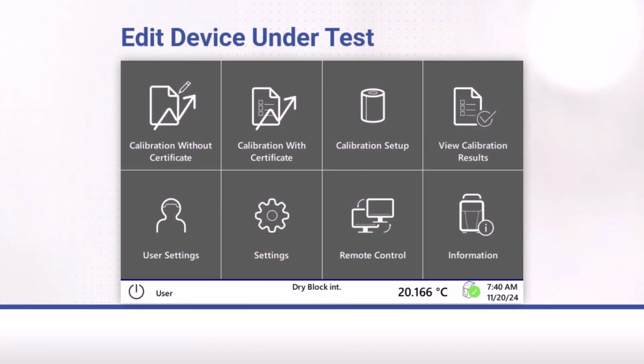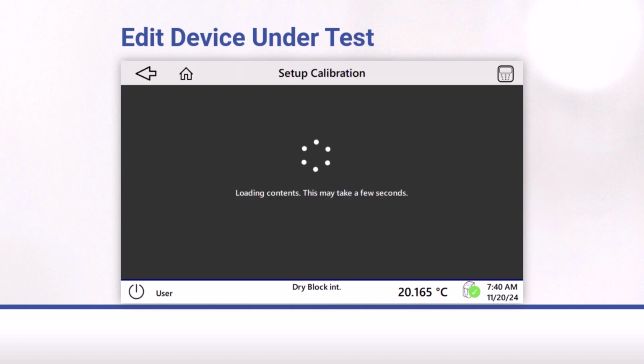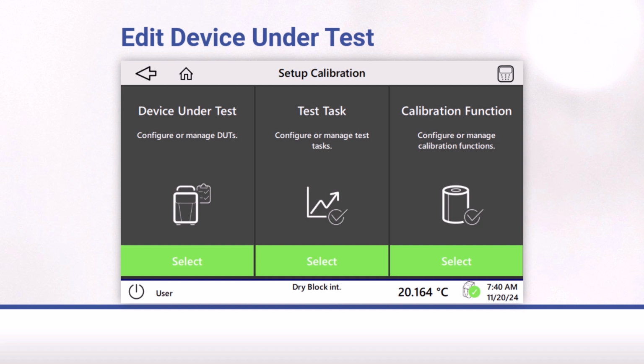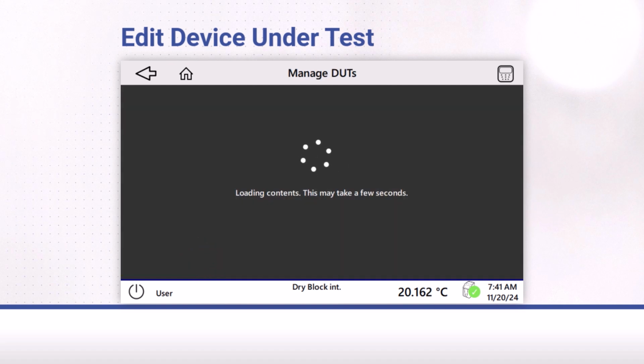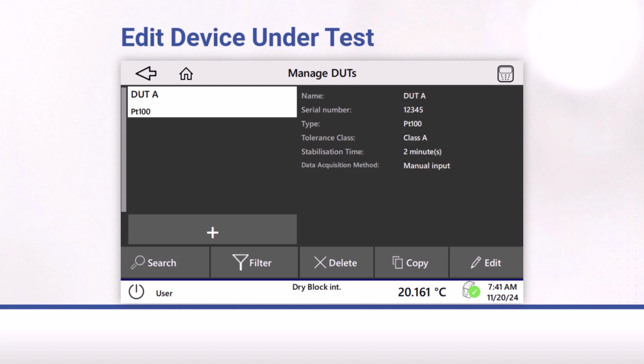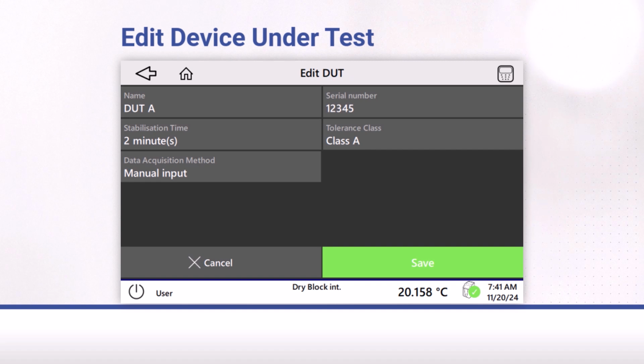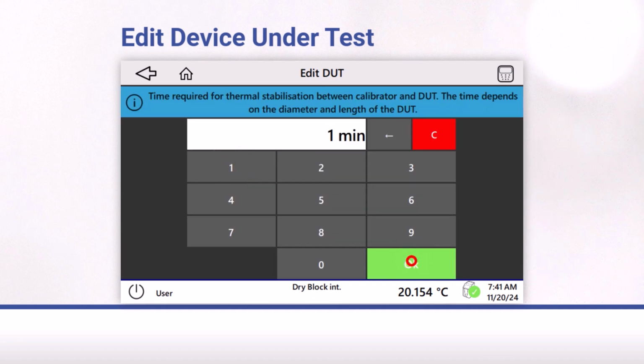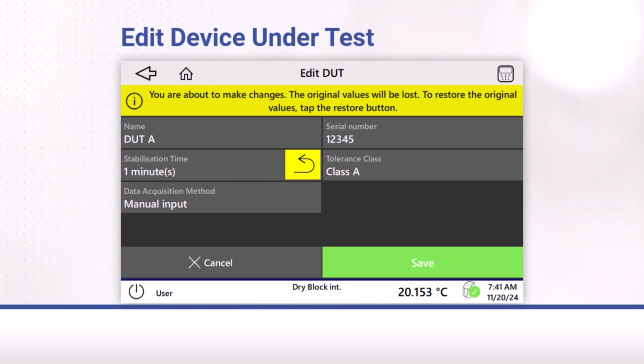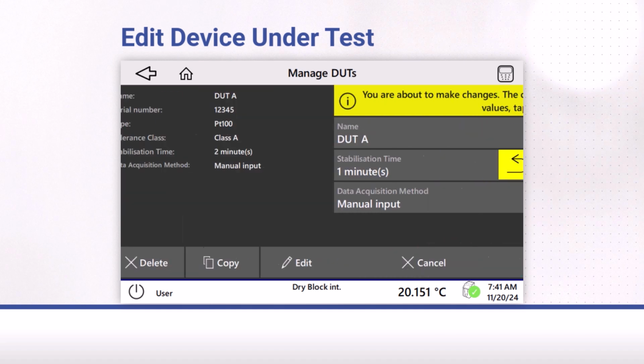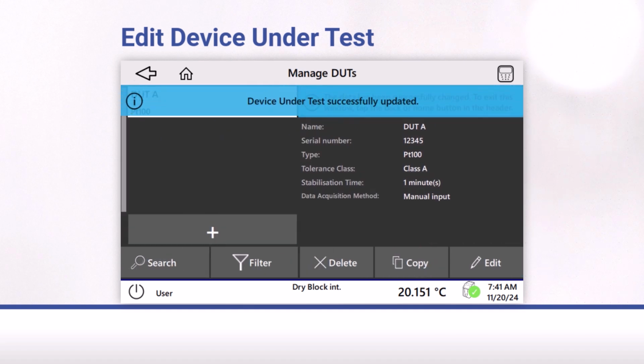From the main screen, tap Calibration Setup. Under Device Under Test, tap Select. Select the device under test that you want to edit from the list. Tap Edit. Depending on the type of DUT, you can edit different properties. To change a property, tap the appropriate field and make the changes. When you are finished making changes, tap Save. Your device under test has been successfully updated.